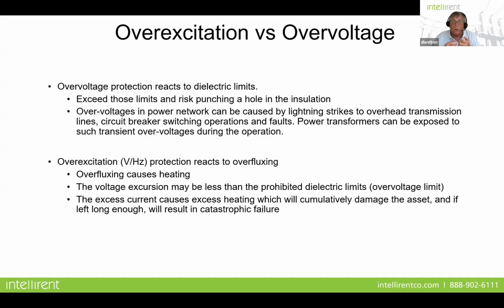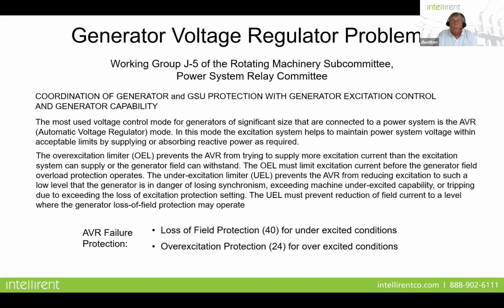So the excess current causes excess heating, which will cumulatively damage the asset. And if it's left there long enough, it could actually result in a catastrophic failure. Well, how does this happen? One of the reasons you see this setting, volts per hertz, on a GSU is because it's an event that happens to the generator when it is direct connected to the transformer.